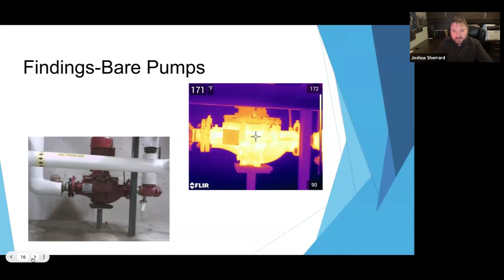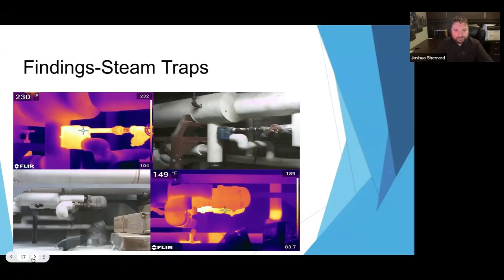Steam traps are something most facilities that still run steam deal with. I know we're in a time where a lot of facilities are trying to get away from steam, but some just can't do that collectively right now, they have long-term plans for it. In the meantime, if you're doing an annual steam trap audit and need access, we can recommend a removable system with 2 or 3 Velcro straps that conserves energy 364 days a year, and you just remove it for that one day you do your annual inspection.